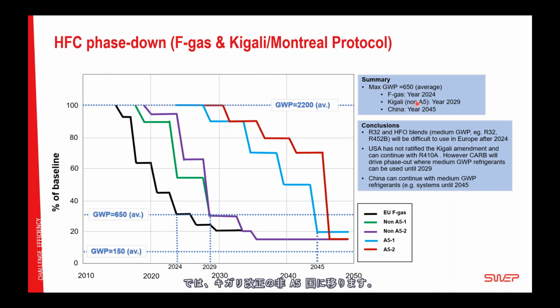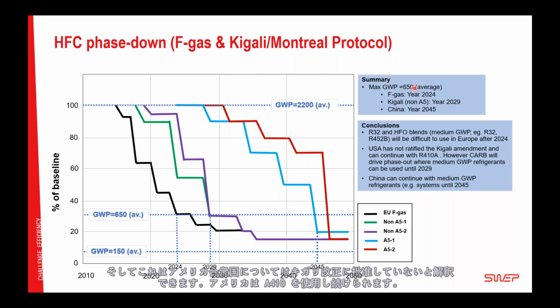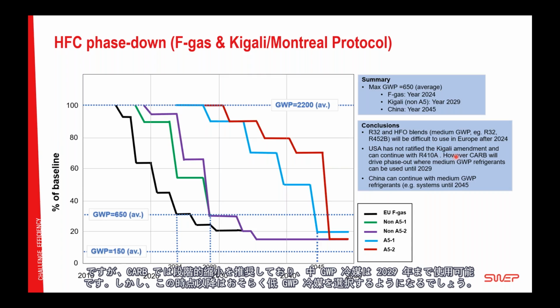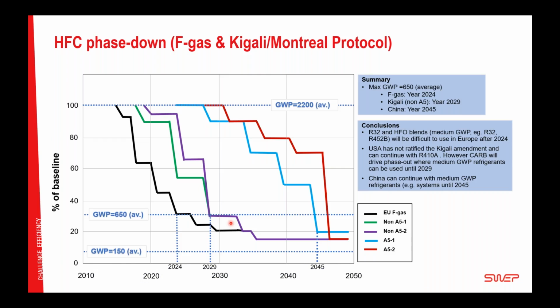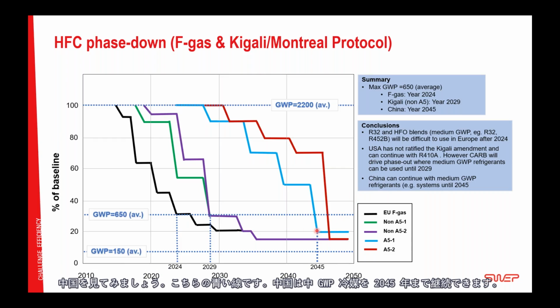Moving over to Kigali non-A5, we have 2029 as the breakpoint for 650. And this can be interpreted for US. They have not ratified the Kigali Amendment, and they can continue with 410A. However, with CARB, there will be a phase-out drive where medium GWP refrigerants can be used until 2029. However, after this point, there will probably be a selection of low GWP refrigerants instead. Looking to China, which is the blue line here, they can continue with medium GWP refrigerants until 2045.